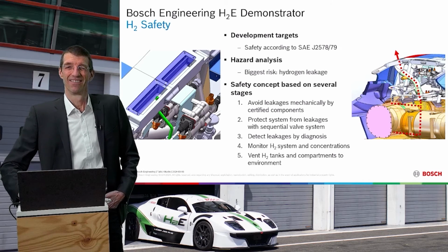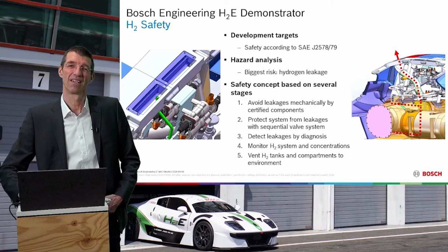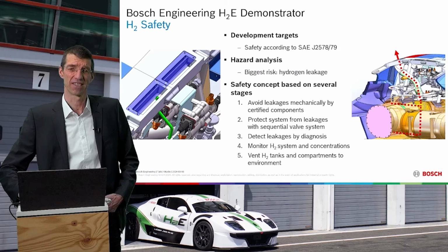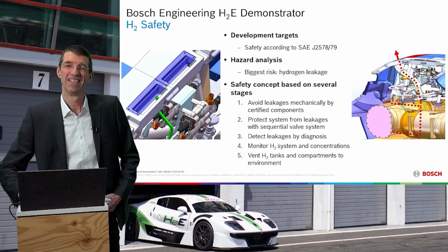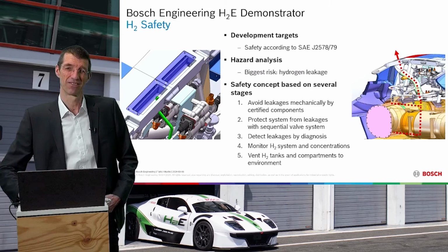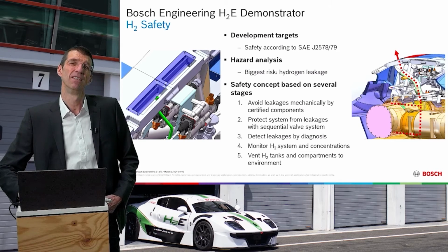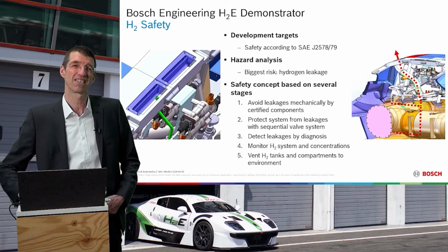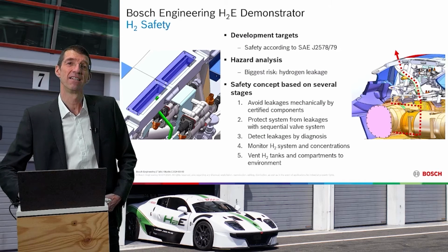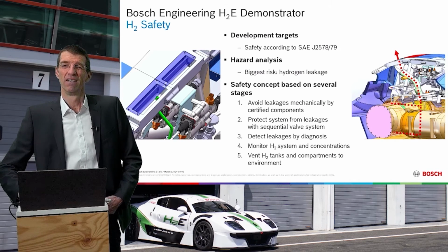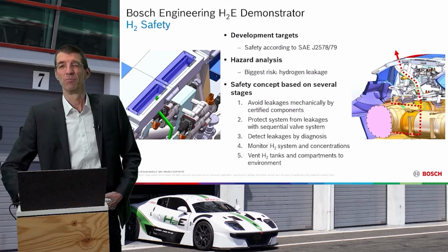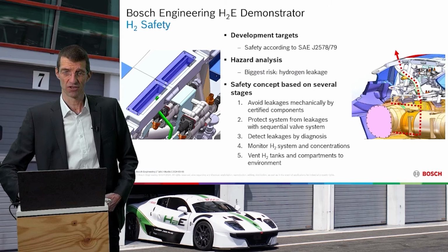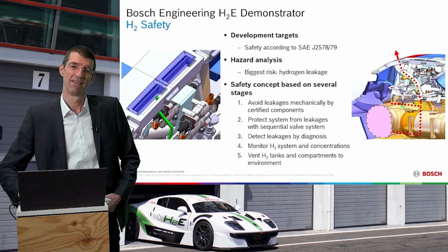The biggest risk, of course, is hydrogen leakage, so we introduced a safety concept based on several stages. First, avoid leakage mechanically with certified components. Then protect the system from leakage with a sequential valve system - for example, on-tank valves, excess flow valves, pressure relief valves, and system isolation valves. We detect leakage by diagnosis, monitor the hydrogen system and concentration, and finally vent the hydrogen tanks and compartments to the environment.